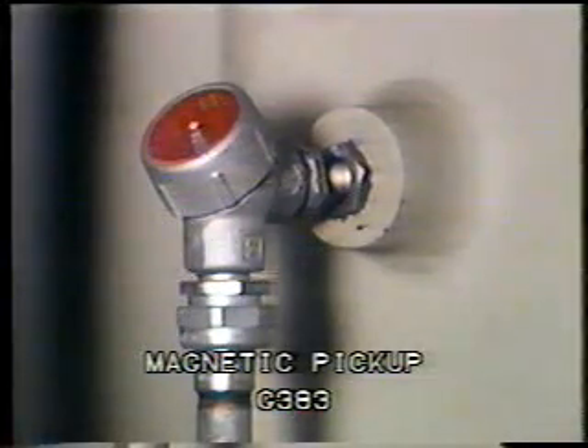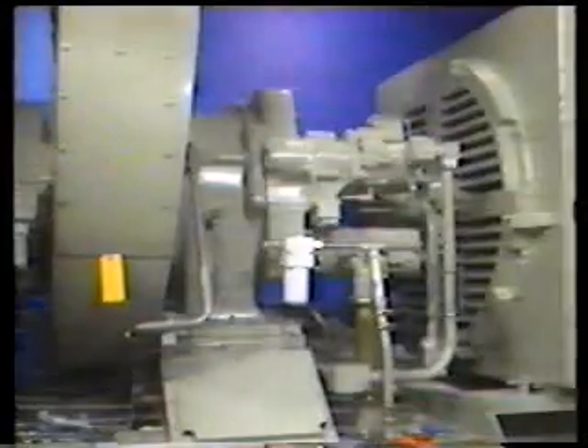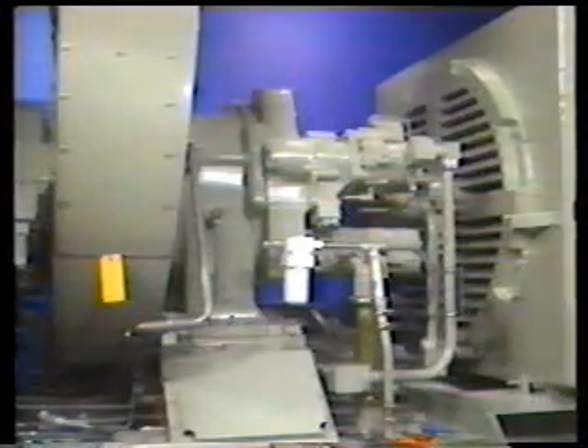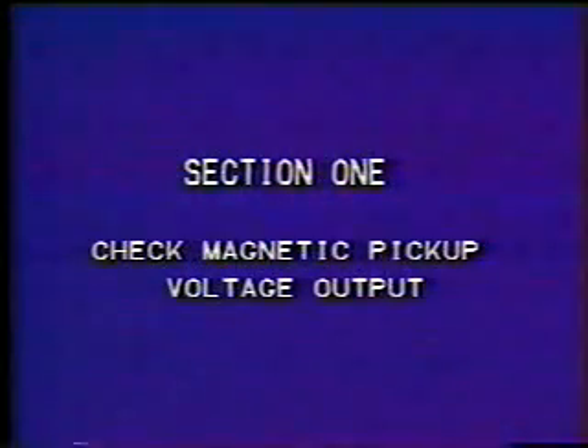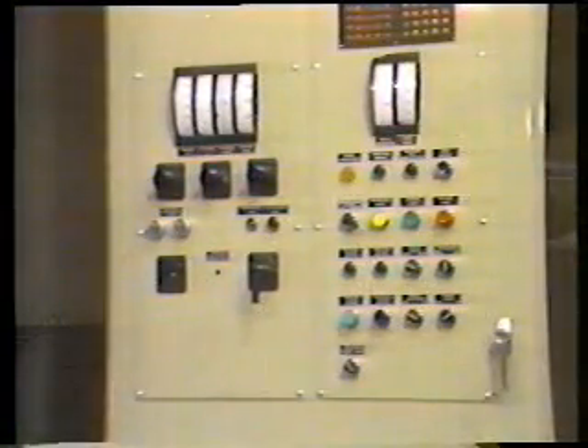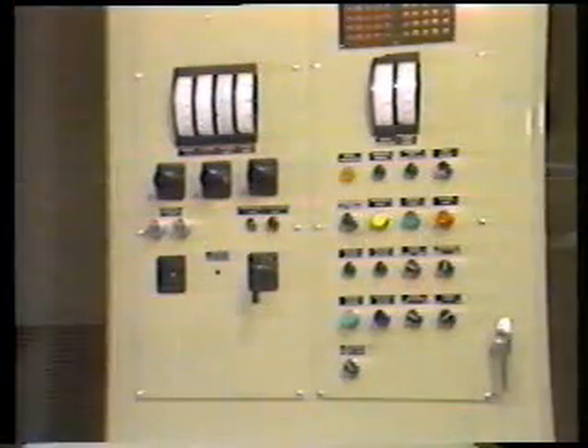They should be inspected after each 4,000 hours of operation. The following procedure will be demonstrated on G383 only. However, the same procedures will also apply to G351. Check your operation and maintenance instructions for warnings and safety precautions prior to performing maintenance. The voltage output of the magnetic pickup should be checked as part of the intermediate inspection.